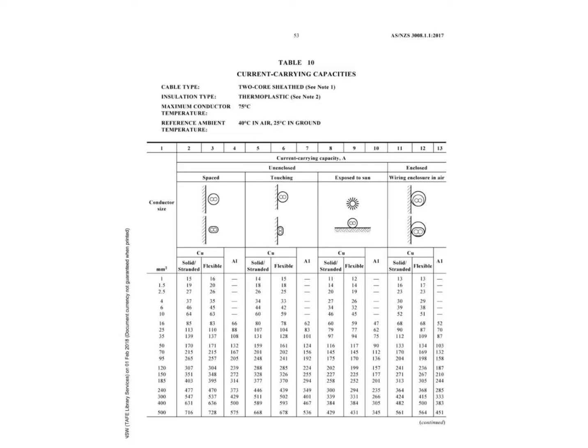AS3008 has a clear provision on the current that can be carried by cables. Under different conditions, it can be seen from the following table that in sunny weather, when the conduit is close to the wall surface, the carrying current of a 6 square millimeter wire is 39 amperes. The standard models of electrical switches are 16 amperes, 20 amperes, 25 amperes, 40 amperes, 63 amperes, 100 amperes. If the maximum output current of the inverter in the photovoltaic system is less than or equal to 30 amperes, we can choose a 32 ampere AC breaker and so on.